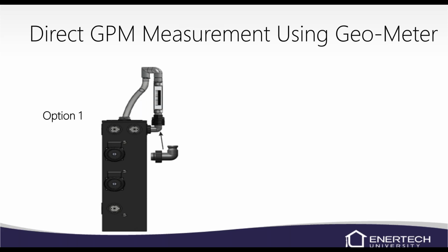On a non-pressurized flow center, the NP series is actually pretty good: if you check pressure drop, it's pretty close to the actual flow. When we had the QT flow centers, they were not real accurate on checking pressure drop with flow. So you would need a flow meter tool. And this is option one for measuring the flow with the tool itself. Obviously, this is not going to really stay in the system. You're just basically pulling out of the flow center, going through the flow meter, and then dumping right back into the top of that flow center.